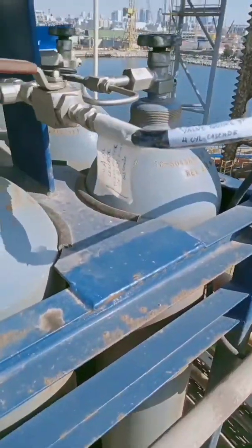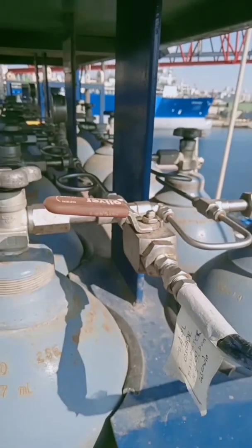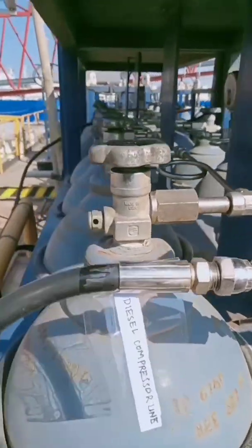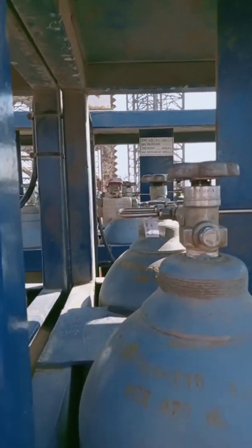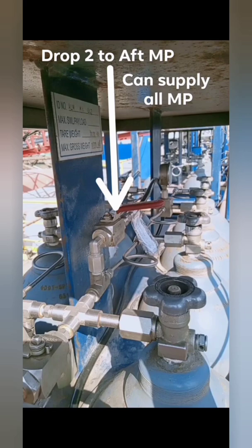This line goes to the four-cylinder cascade rack. If you want to top it up, you need to open this valve. This is the diesel compressor line — if you want to top up all the system using the diesel compressor, open that valve. Make sure all the cylinder valves are closed. We have three direct supplies coming from the cascade: the first goes to the reception master point, the second to the aft master point, and the third to the port master point. You can open any of these three drops to supply or activate the system.